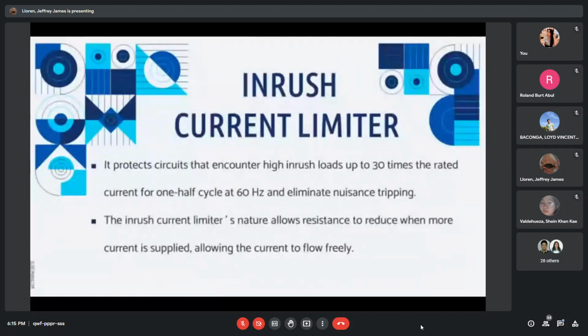Inrush current limiter. An inrush current limiter protects circuits that encounter high inrush loads up to 30 times the rated current for 1/2 cycle at 60 Hz, and it also eliminates nuisance tripping. The inrush current limiter's nature allows resistance to reduce when more current is supplied, allowing the current to flow freely.